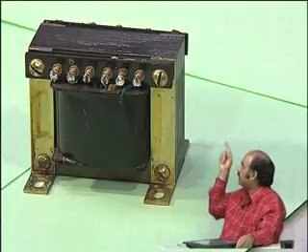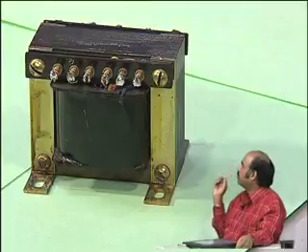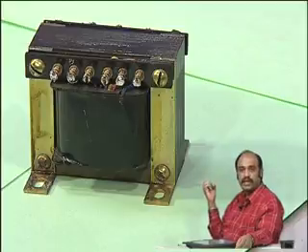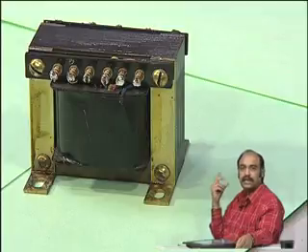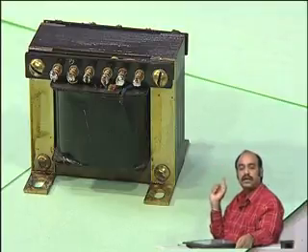And see that all practical transformers will have the core, the solid bulk of the core, laminated, and then after laminating, all the air pockets are vacuumed out and then it is varnished. So, that black or darkish color is due to the varnish.